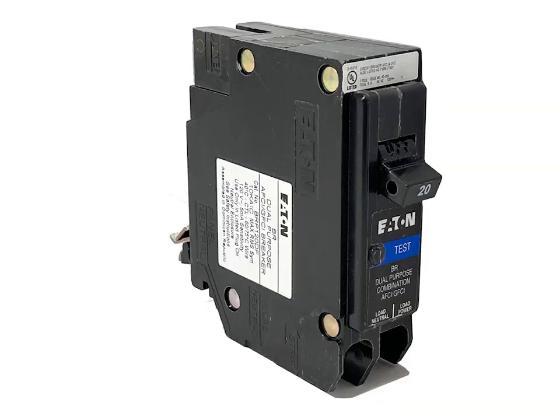Other electrical notes. National Electrical Code has requirements for arc fault circuit interrupter, AFCI, and ground fault circuit interrupter, GFCI, line protection. Almost all circuits will require either AFCI or GFCI, and many require both. This can be most easily accomplished by using dual-purpose combo AFCI/GFCI circuit breakers. AFCI breakers are required on 15 or 20 amp 120 volt circuits. GFCI breakers are required on 125 volt to 250 volt receptacles supplied by single phase branch circuits rated 150 volts or less to the ground.